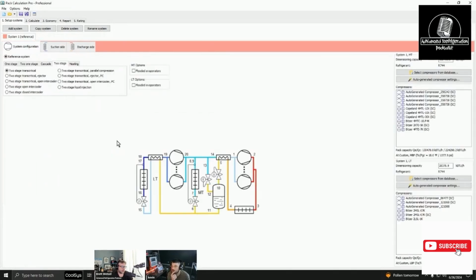We need to talk to Bob. Tell you what, the heat exchangers on the drop legs absolutely suck, especially if you're using it for suction reheat. Oh man, is it terrible. Why? Because you just don't get that much, especially if it's wintertime, you're SOL. When it's wintertime, your flood back control is non-existent. But summertime, it's not as bad. But wintertime, you might as well not even have it.